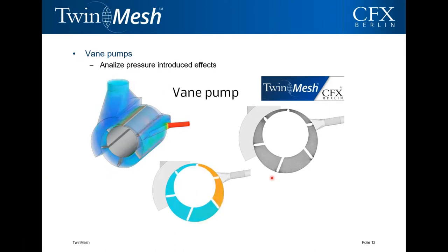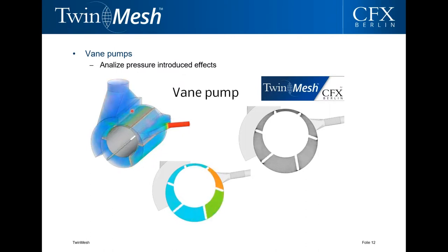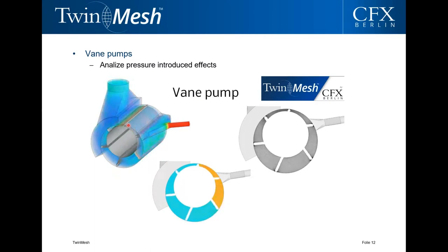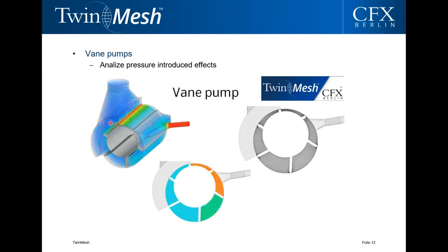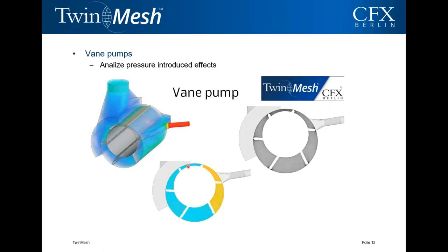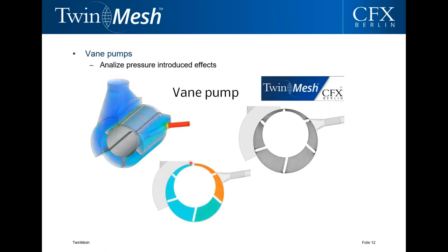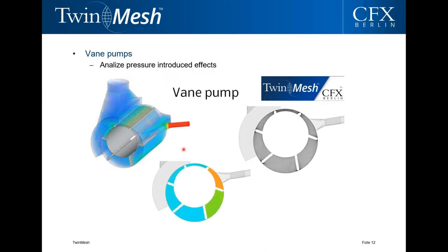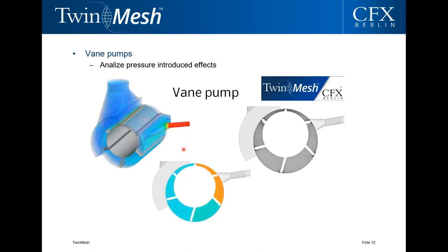Here we see a simulation of a vane pump where pressure-induced effects are visible. As a chamber connects to the pressure port, gas is ejected at high velocity due to over-compression. The center animation shows the corresponding pressure field exceeding a certain value before connecting to the ambient-pressure port. The right animation shows the grid, which could be the basis for an optimization task to eliminate the over-compression.